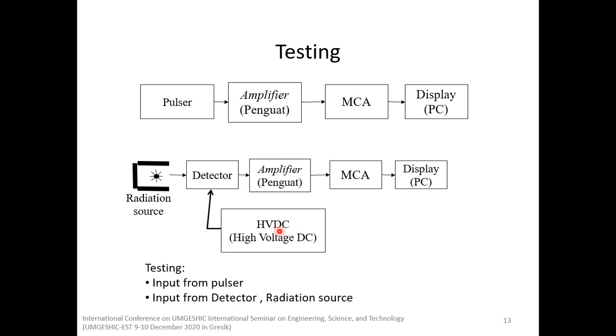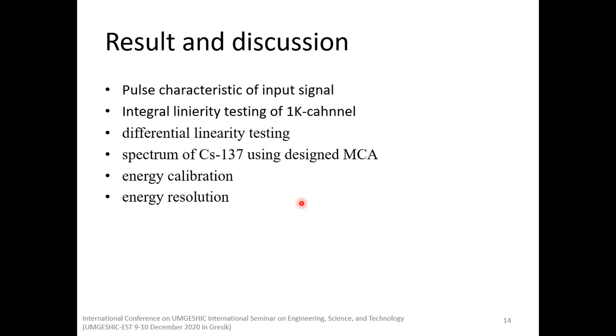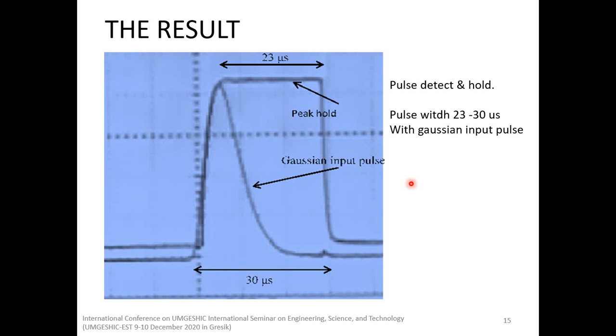The result and discussion. The following results are related to the pulse characteristic of the input signal, integral linearity testing of one kilo channel, differential linearity testing, spectrum using cesium 137 with the designed MCA, energy calibration, and the energy resolution. Here is the pulse characteristic of the input signal. The pulse width is 23 until 30 microseconds with a Gaussian input pulse.